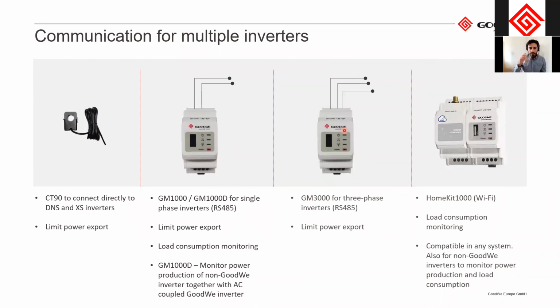Here are some communication devices. Sorry for this, it should maybe be more single inverters here, not multiple inverters. These are different communication devices that you can add to the inverters. For the storage inverters, everything is included, so it's not really necessary. But for the grid tie inverter, as I said before, the CT90s can be connected directly to the DNS and XS inverters to limit the power export.